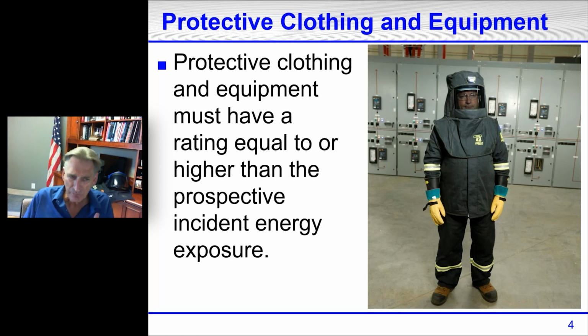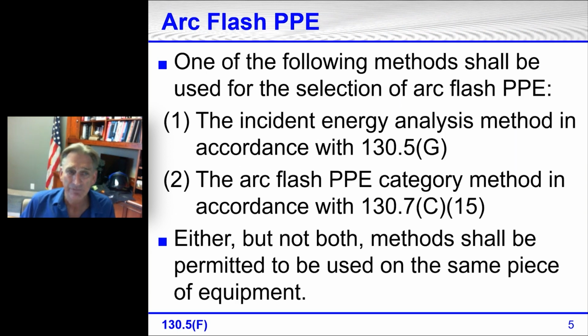Protective clothing and equipment has to have a rating equal to or higher than the prospective incident energy exposure. This is a friend of mine, Terry Becker in Canada, showing this Oberon suit. Arc flash PPE is in 130.5. So let's talk about arc flash first, and then we'll talk about shock. In determining what we need to wear, there are a couple of things that can be done. In fact, it says in 130.5(F), one of the following methods has to be used for selection of arc flash PPE. Number one, the incident energy analysis method in accordance with 130.5(G).